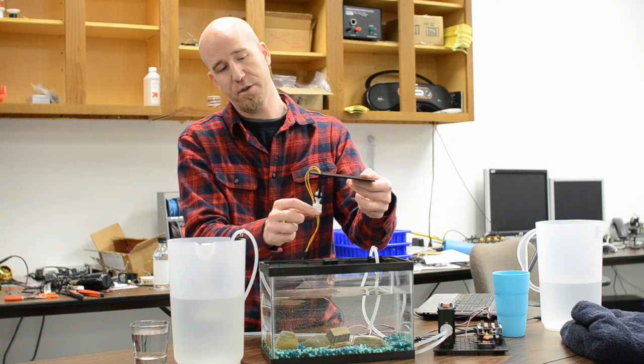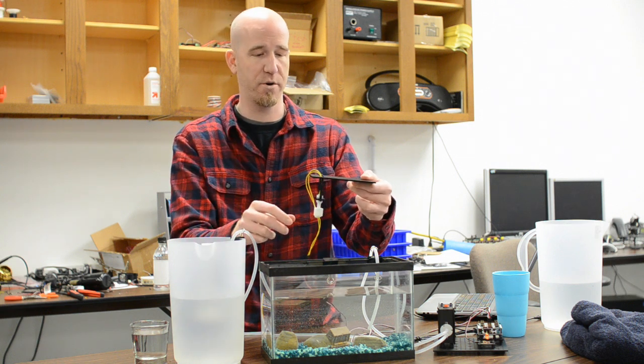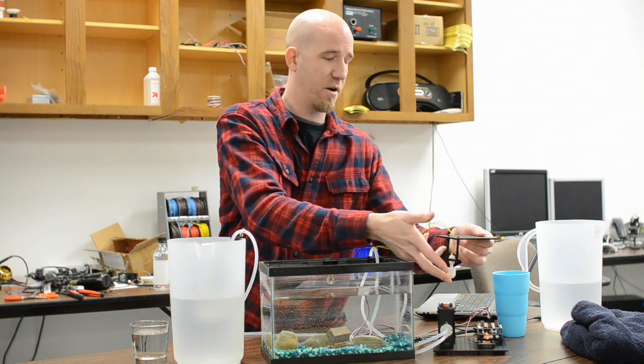The way a float switch works is you have a little float and oftentimes there's a magnet or something in there and a reed switch on the inside so that there's nothing exposed. And you can see that when I move it up and down the light goes on and off.